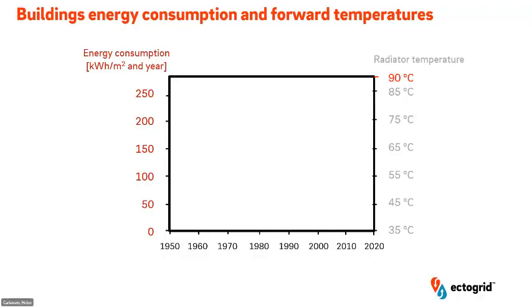In old buildings, we have an energy demand that is quite high, but we also have a forward temperature in the building that is quite high, many times because the source of generation was combustion. In new buildings, the energy consumption is much lower, but also the supply temperature in the building for comfort heating is much lower. So for instance, if you have underfloor heating in a newly built area, the supply temperature might vary between 30 and 40 degrees. In an older building that is made for gas boilers, the supply temperature might be 80 degrees. But for new buildings, 80 degrees is no longer necessary.